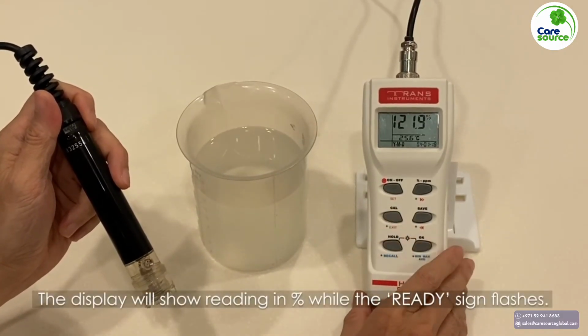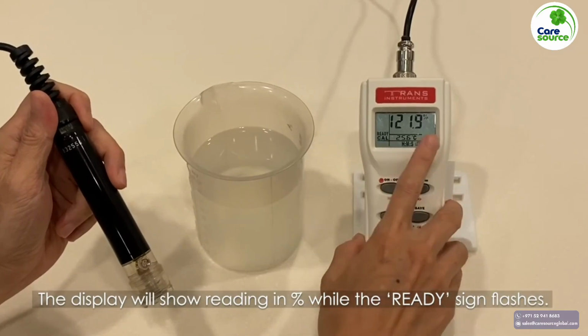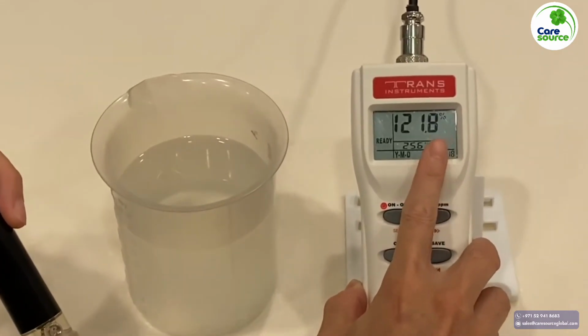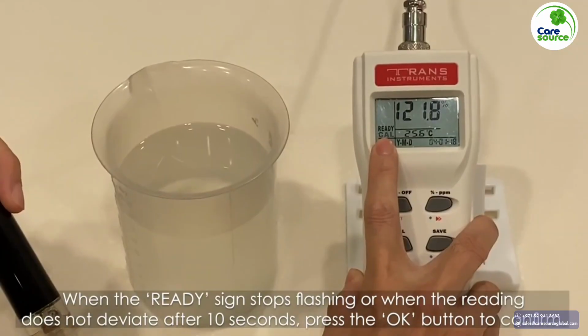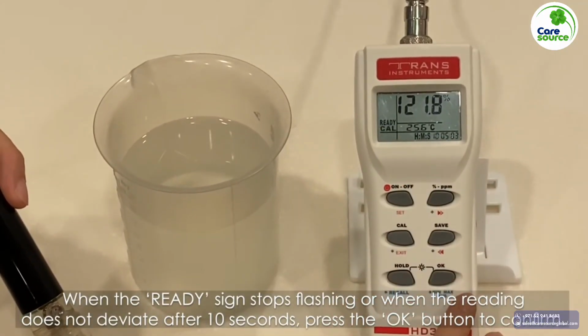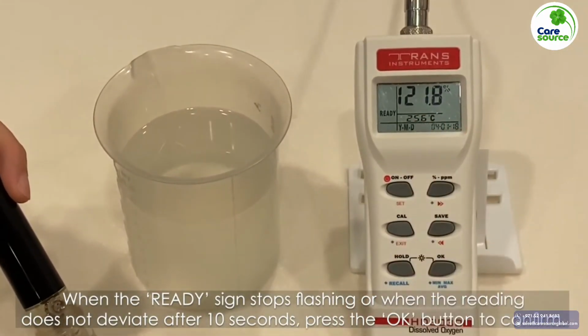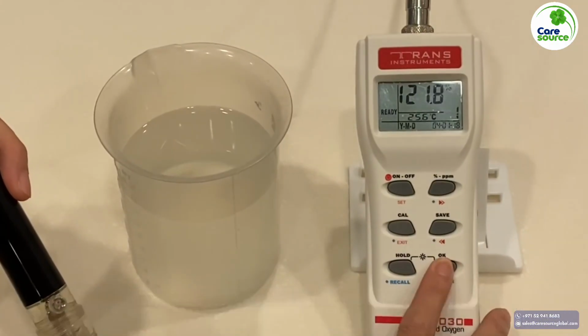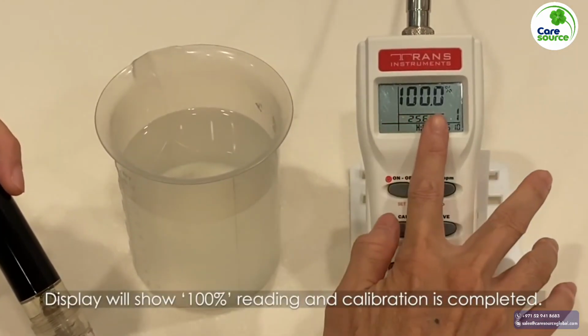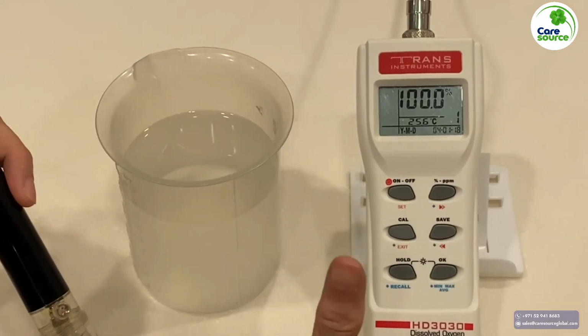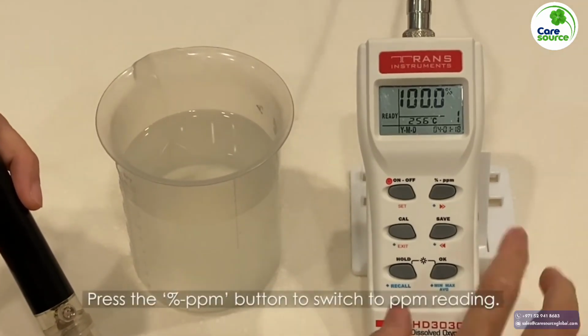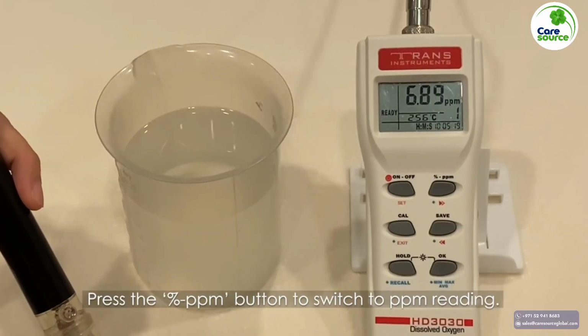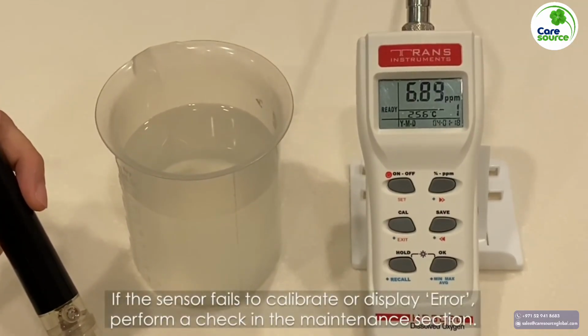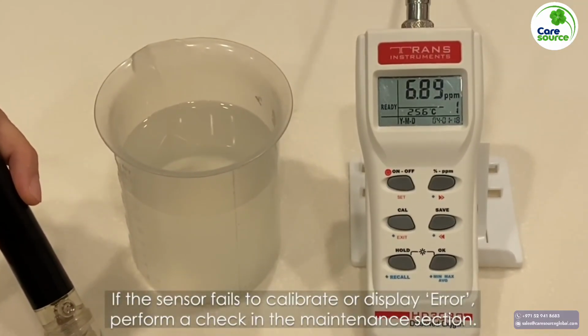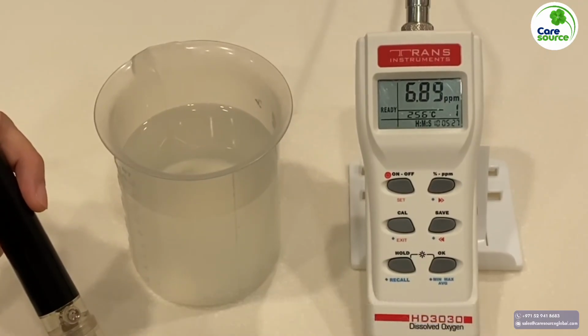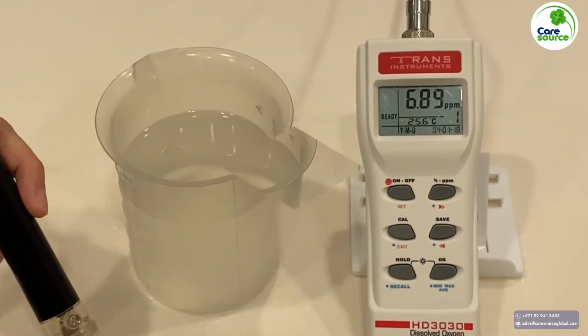The display will show reading in percentage while the ready sign flashes. When the ready sign stops flashing or when the reading does not deviate after 10 seconds, press the OK button to confirm. Display will show 100% reading and calibration is complete. Press the percentage ppm button to switch to ppm reading. If the sensor fails to calibrate or displays an error, perform a check in the maintenance section. We can now proceed to take a measurement in the water.